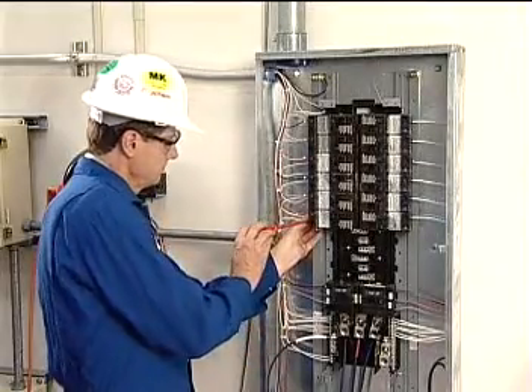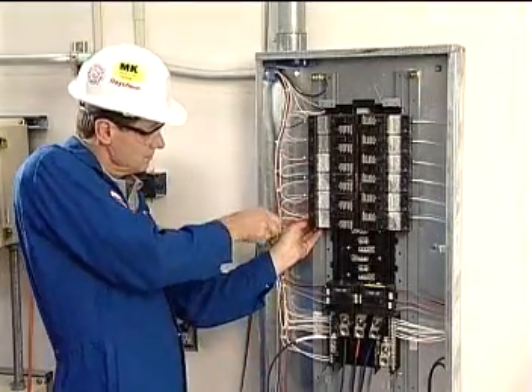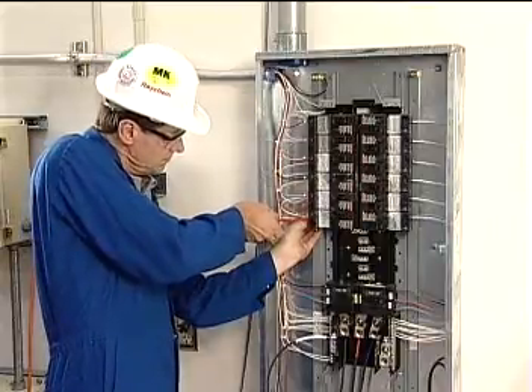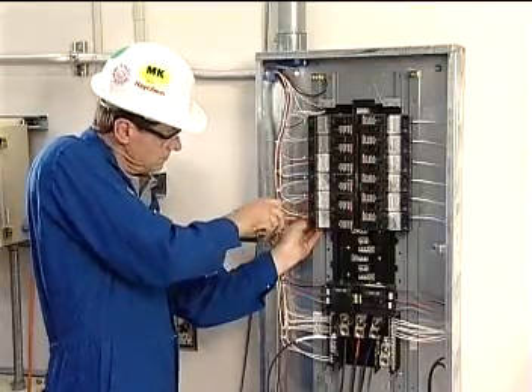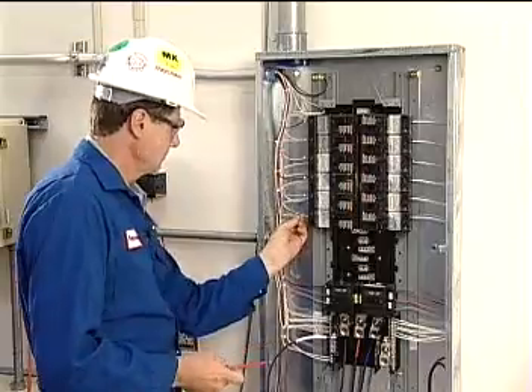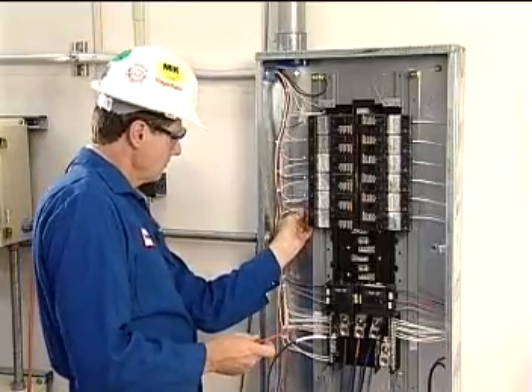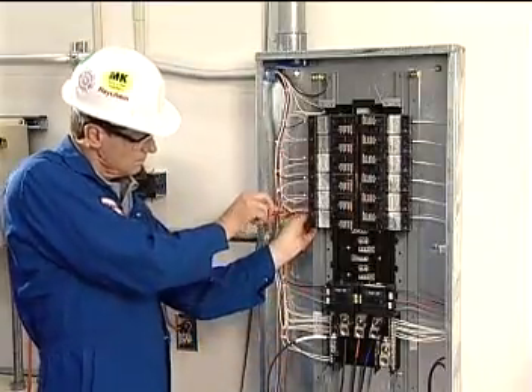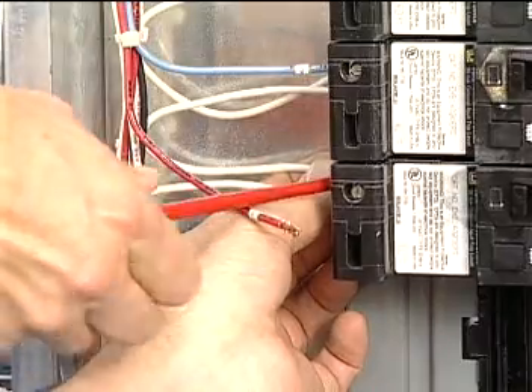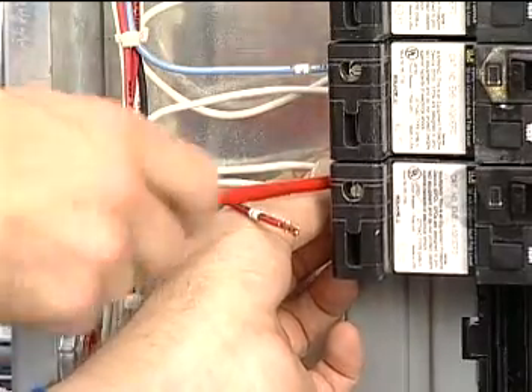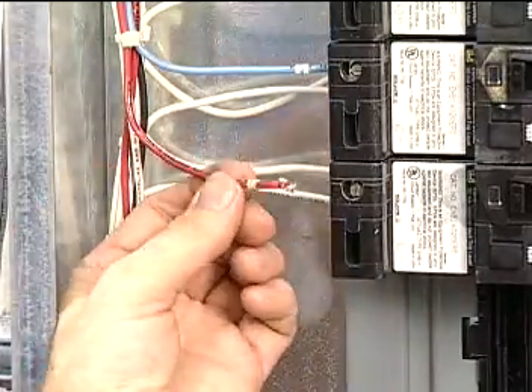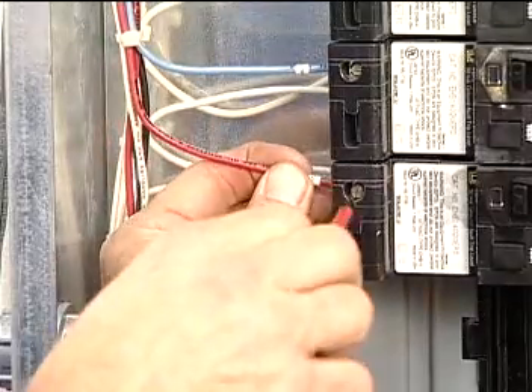Installing ground fault circuit breakers is a little different than standard thermomagnetic circuit breakers. A ground fault circuit breaker has an electronic circuit that senses a ground fault condition and trips the breaker under conditions that may not trip a conventional overcurrent breaker. It requires that a neutral wire, either run separately or supplied as a pigtail, be connected from the breaker to the neutral bus of the circuit breaker panel.